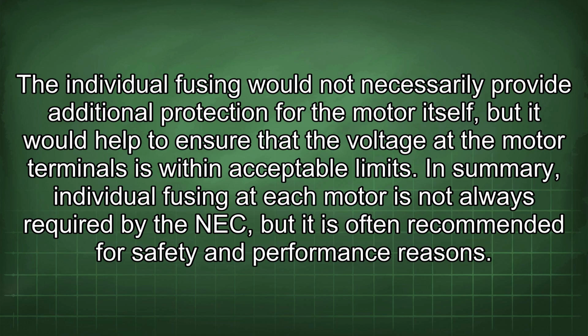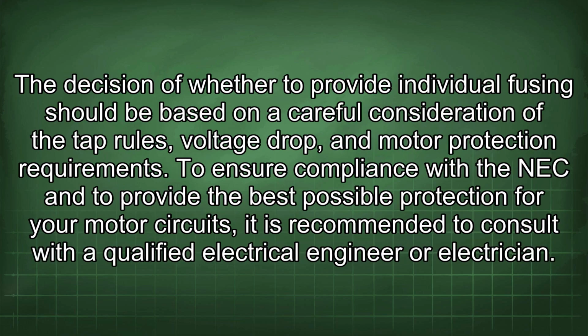In summary, individual fusing at each motor is not always required by the NEC, but it is often recommended for safety and performance reasons. The decision of whether to provide individual fusing should be based on a careful consideration of the tap rules, voltage drop, and motor protection requirements.